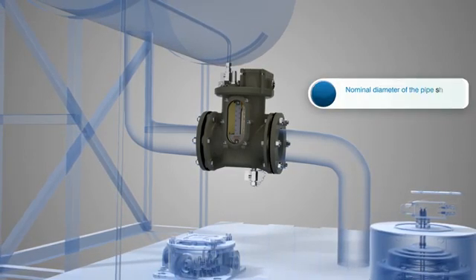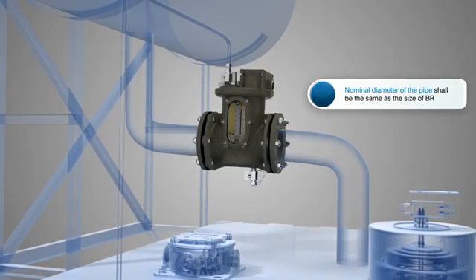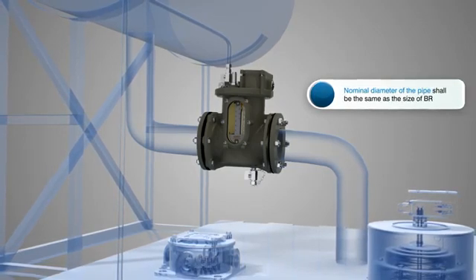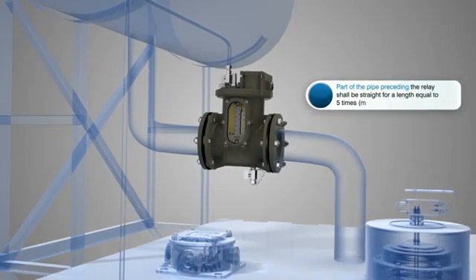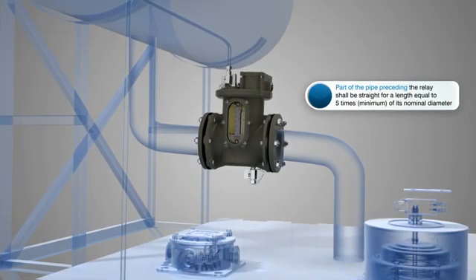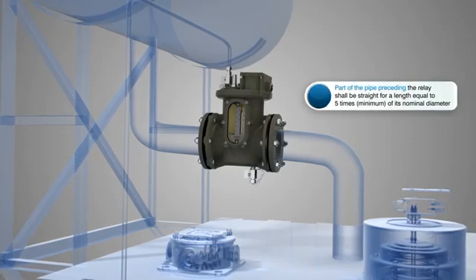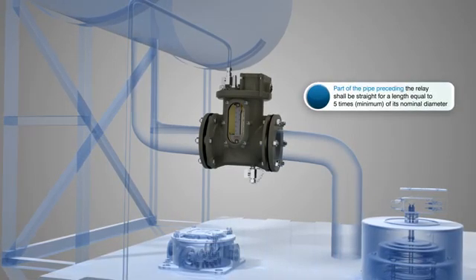The nominal diameter of the pipe shall be the same as the size of the Buchholz relay. The part of the pipe preceding the relay shall be straight for a length equal to 5 times minimum of its nominal diameter.